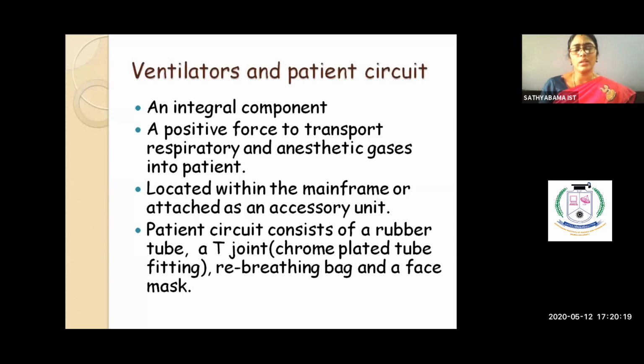So why do I need a ventilator in an anesthesia machine? Obviously you are unconscious, right? So you have to breathe and be given these gases and all that. All that is done using a ventilator. So whatever oxygen is required, and taking out the carbon dioxide, the entire part will be taken up by your ventilator, right? It can be a part of your mainframe unit. Few anesthetic machines are there wherein the ventilators are inside or part of that particular frame itself. Otherwise, it can be an accessory unit. So you keep the ventilator beside your anesthesia machine, and then you will be using it.